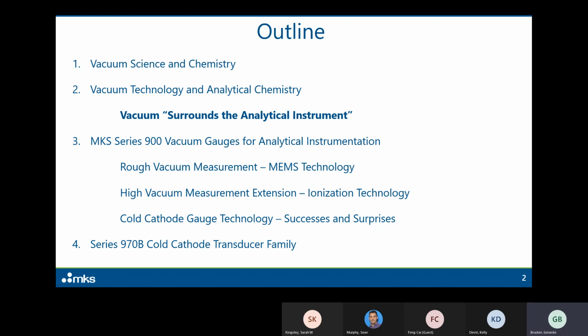And of course, because I'm on the pressure measurement side, we'll be talking about how we surround the chamber with vacuum measurement instrumentation, or pressure measurement instrumentation. The focus is going to be on the MKS Series 900 of vacuum gauges, which is very well suited for analytical instrumentation. It's not the only thing it's good for, but it's very well fitted, as you're going to see, based on the requirements of the industry for that particular application.